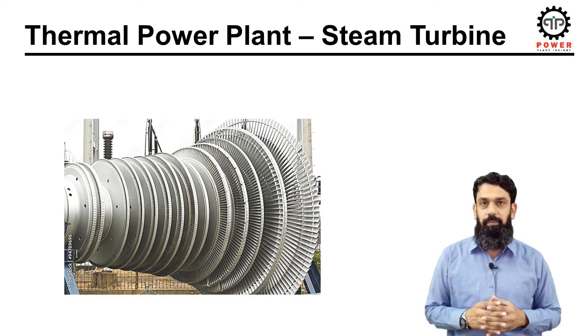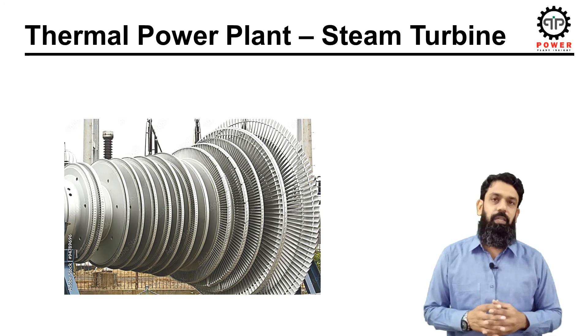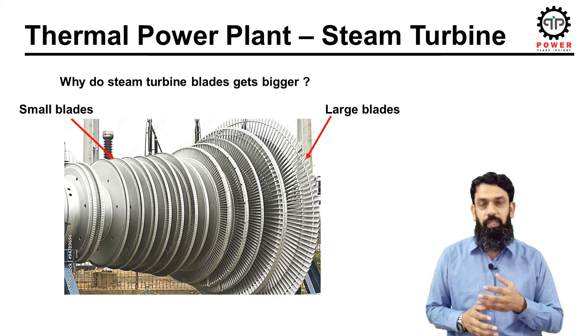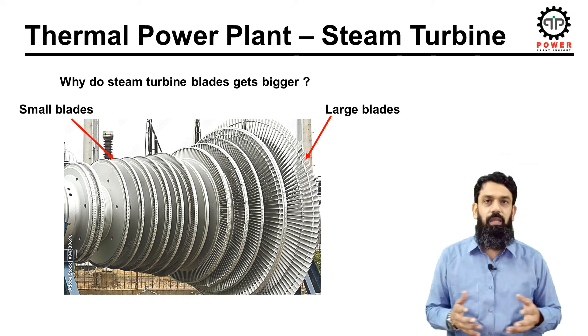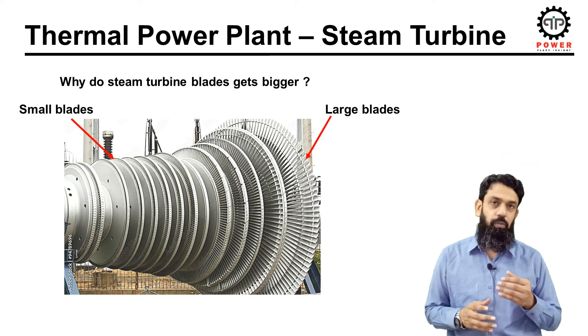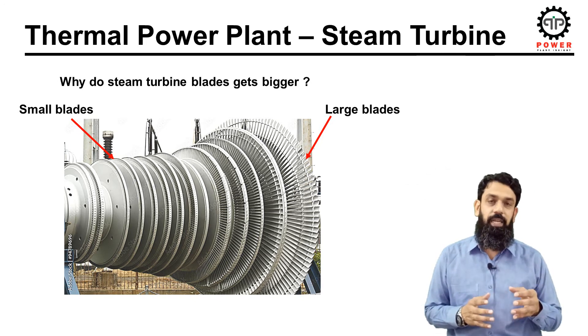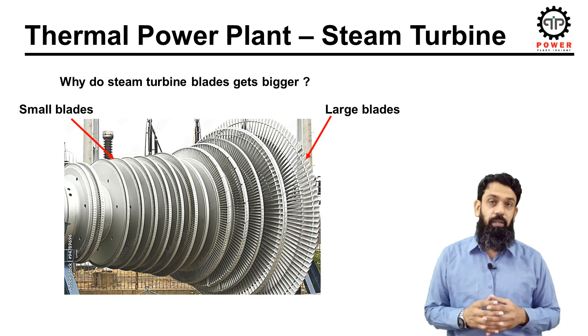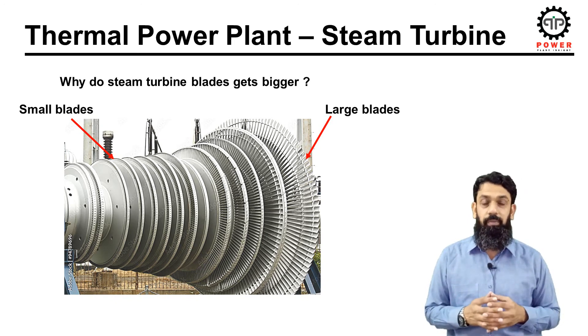This is a picture of a turbine rotor. Looking at the picture, a question comes to mind: why are the rotor blades of the last stage of the turbine bigger compared to the blades of the first stage? The answer is simple. As steam moves through the turbine rotor, it loses its pressure and thermal energy and ultimately its volume increases. This requires larger diameter and longer blades in the later stages of the turbine to accommodate this increase in volume and extract the remaining amount of energy from the steam.